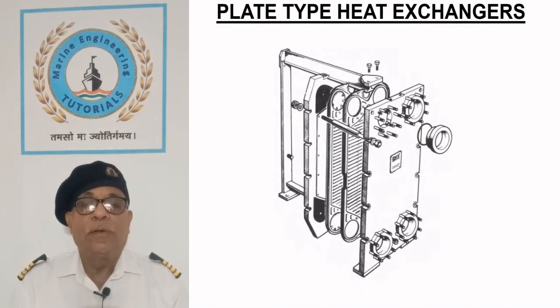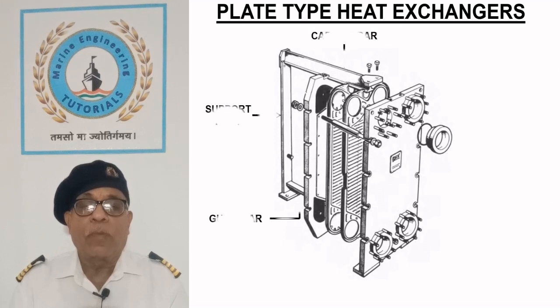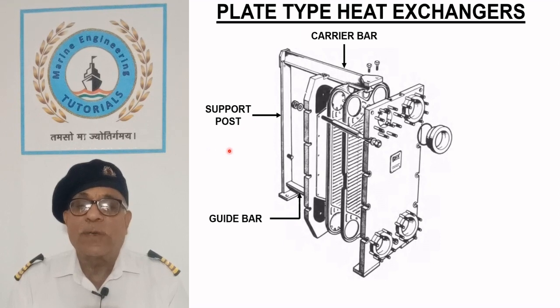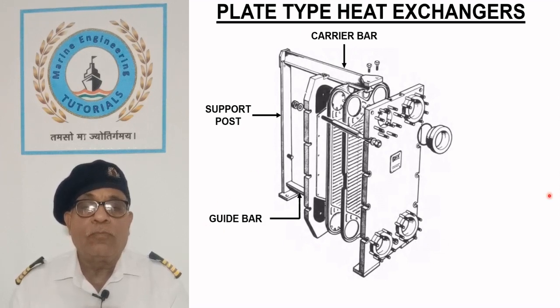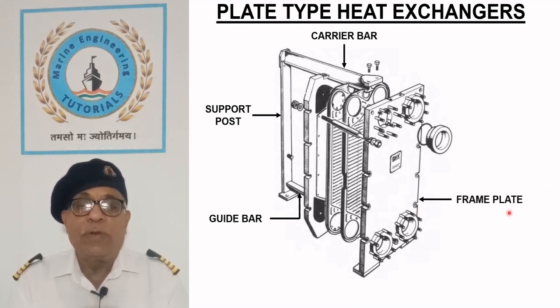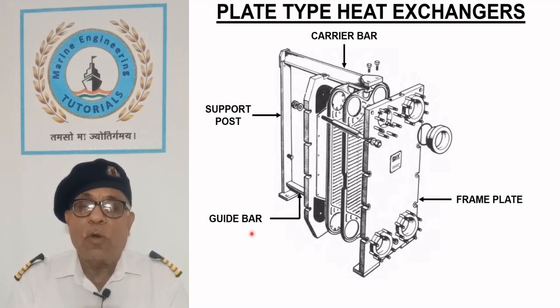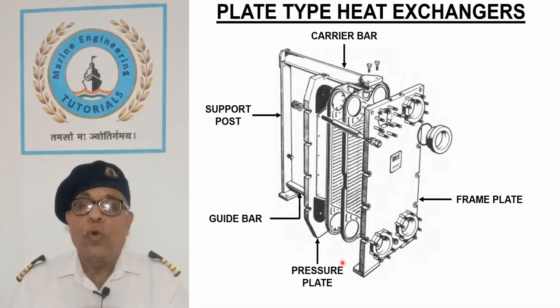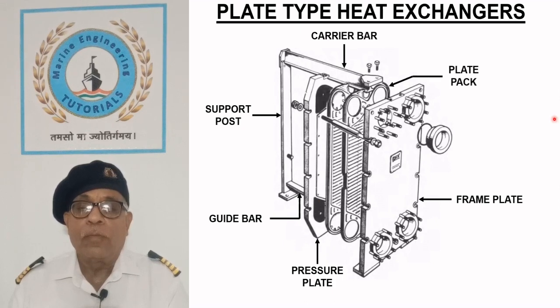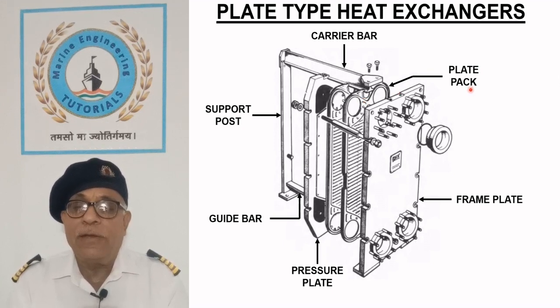Plate type heat exchangers. The sketch shows the construction and assembly of a plate type cooler. The main frame of this cooler consists of a support post which has a carrier bar on the top and a guide bar at the bottom. The frame plate is secured between the carrier bar and guide bar either on the front side or rear side. Four branch pipes on the frame plate provide inlet and outlet connections for the two liquids. A pressure plate holds all the components together. A set of plates are sandwiched between the frame plate and pressure plate.